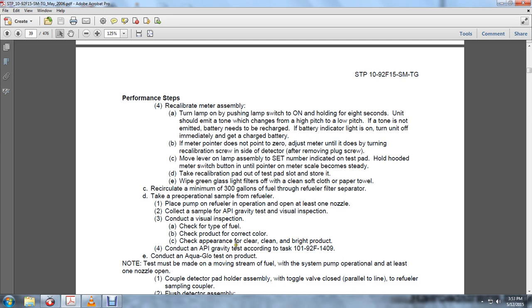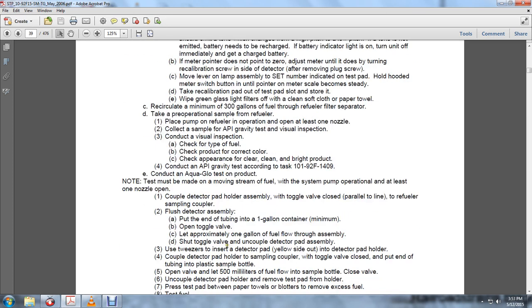Check the API gravity test according to task 101-92F-1409. Conduct an aqua-glo test, and the product test must be made on the moving stream of fuel with the system pump operational and at least one of the nozzles open. 1. Keep the coupler detector pad holder assembly toggle valve closed, parallel to the line of fuel of the sample coupler. Flush the detector assembly. Put in a minimum of one 1-gallon tank container. Open the toggle valve and let approximately 1 gallon of fuel flow through the assembly. Shut the toggle valve and uncouple the detector from the pad assembly.